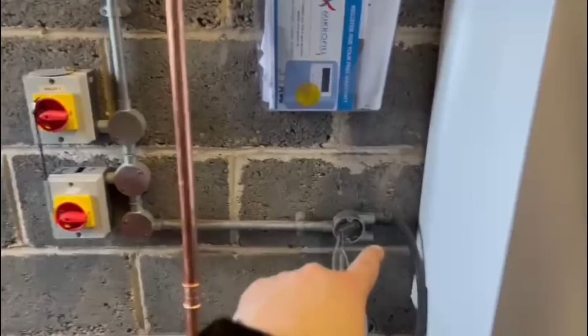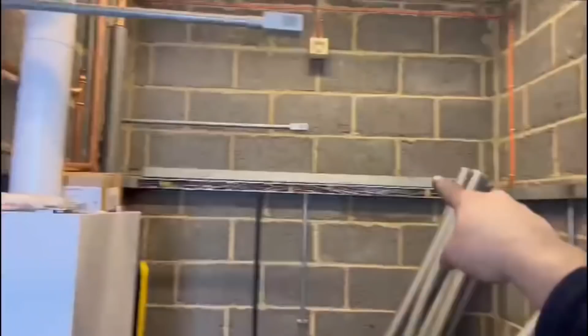So the electrics for the Weishaupt is brilliant. You mainly need a live, neutral and earth. So I've retained the old Kopex off the boiler one, and I'm going to put that live, neutral and earth into this boiler, and then everything else is going to be controlled. So the cylinder loading pump is going to be through the boiler, the heating pump will be through the boiler, the secondary return for the hot water, which is tucked over here. I'm going to find the supply for this fused spur in this containment, which runs all the way around into the BMS panel. I'm going to find that live, neutral and earth, and then I'm hopefully going to squeeze it down that conduit through. So the boiler will control this.